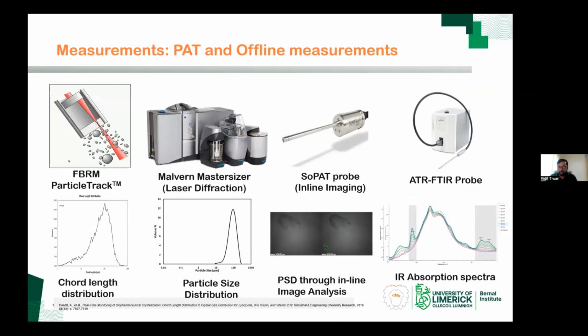Then we move on to the measurement techniques that we use. We have been using some inline monitoring techniques for particle size distribution. Out of these, one is an offline method, which is laser diffraction. And we use that to validate a mathematical model that we use to convert the chord length distributions that we get from an FBRM. This model was developed by our colleagues, Pandit and Ranade. And such mathematical models have their limitations. Some cannot be used for needle-shaped particles because shape factors come into the picture when needle-shaped particles are crystallized. And most of these mathematical models assume chords to be of a circular shape.